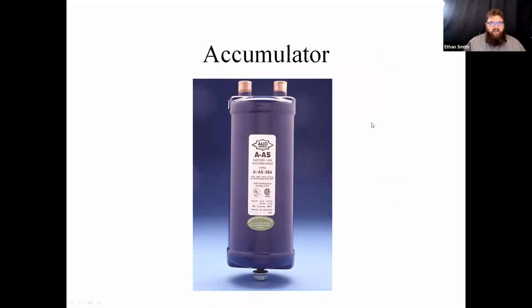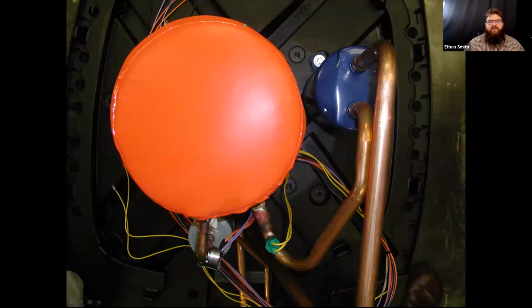We mentioned accumulators. A lot of times you'll see an accumulator attached inside the outdoor unit. This is because during the heating mode, we tend to have a lot of excess refrigerant. Our outdoor coils are much bigger than our indoor coils, and when we're using that indoor coil as a condenser, we may have excess refrigerant. That accumulator is there to protect the compressor from getting liquid refrigerant back to the compressor.